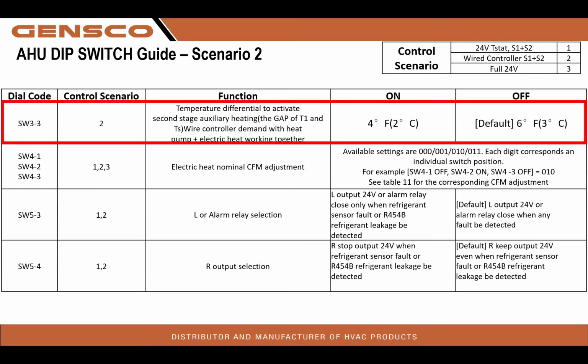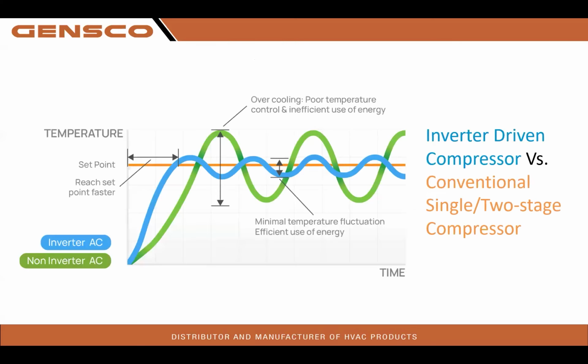If we were going to set our temperature differential, SW3-3, control scenario 2, which is fully communicating. Default is 6 degrees. Dip switch SW3-3 in the on position is 4. Operation. You will notice the difference between an inverter and a non-inverter. Basically, we have a choppy sine wave and a smoother sine wave. And basically what we are doing is controlling it better.